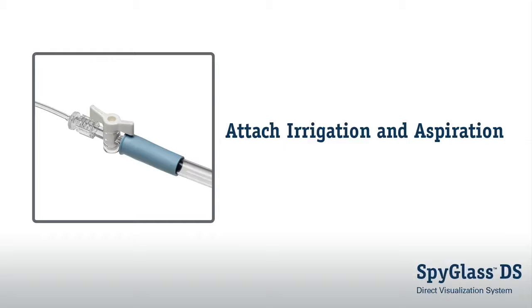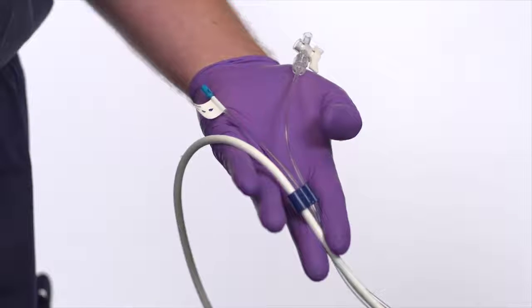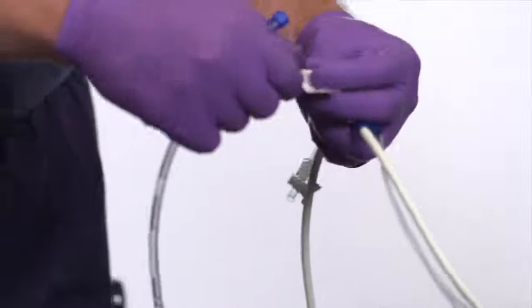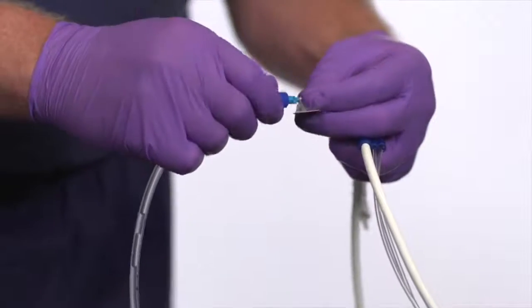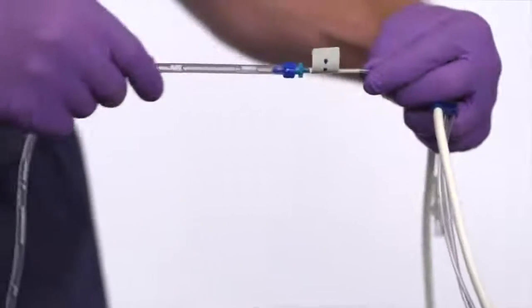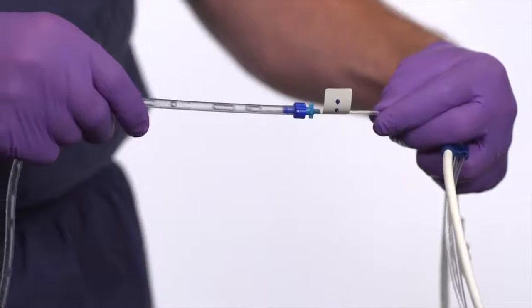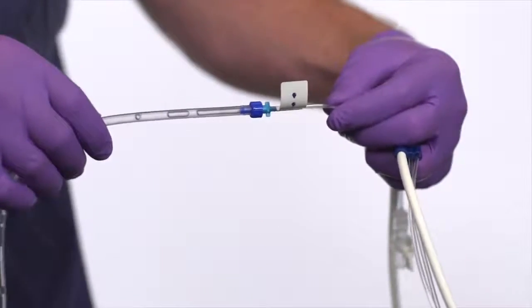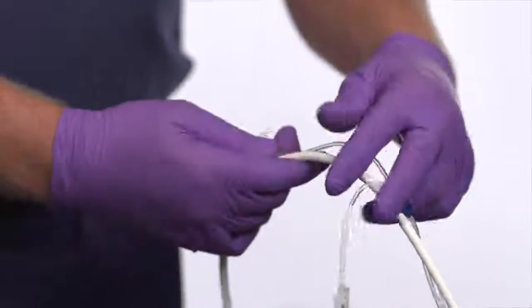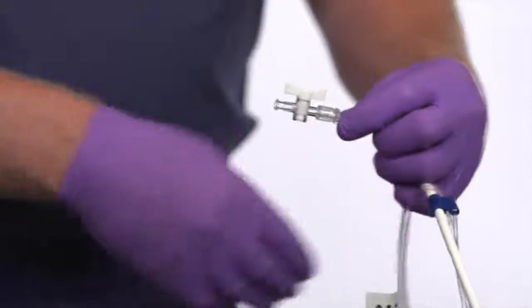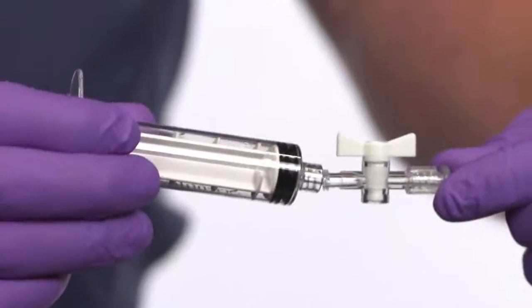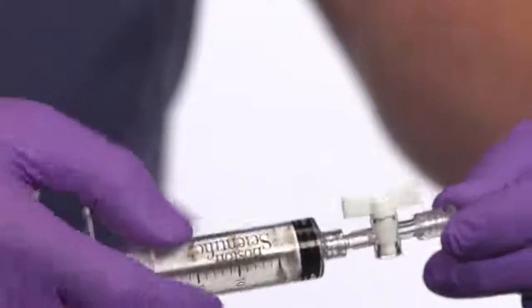Attach irrigation and aspiration. Connect the irrigation tubing to both the irrigation pump and the irrigation port. Apply irrigation to flush the irrigation channels with saline or sterile water. This will minimize air bubbles when later irrigating in the target duct. If desired, connect a suction source to the aspiration port.